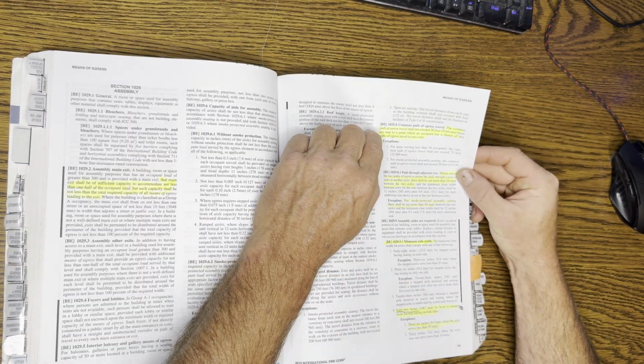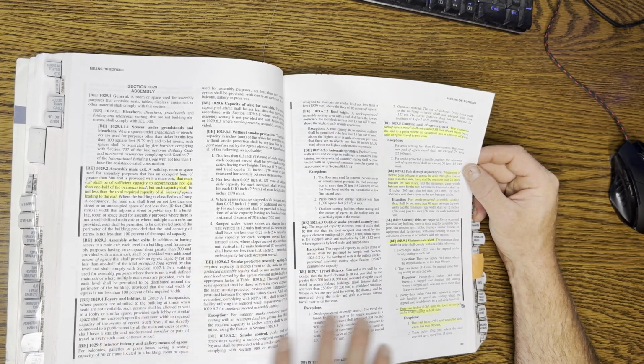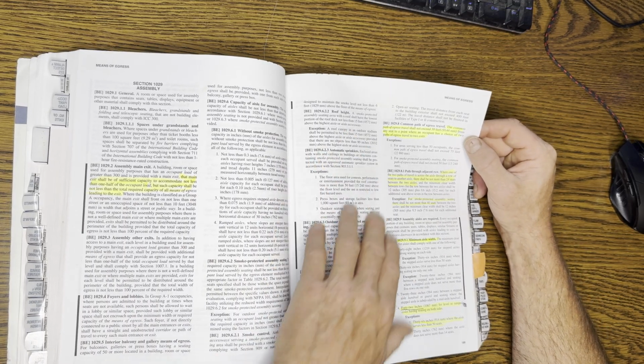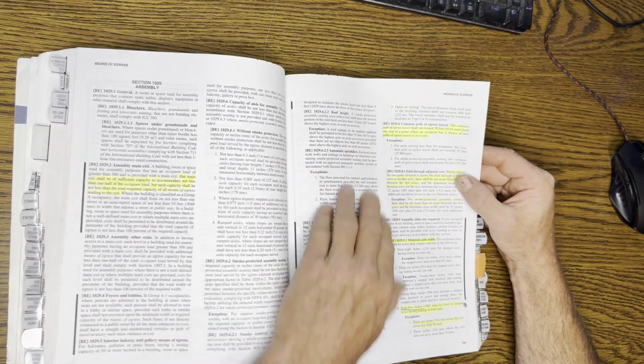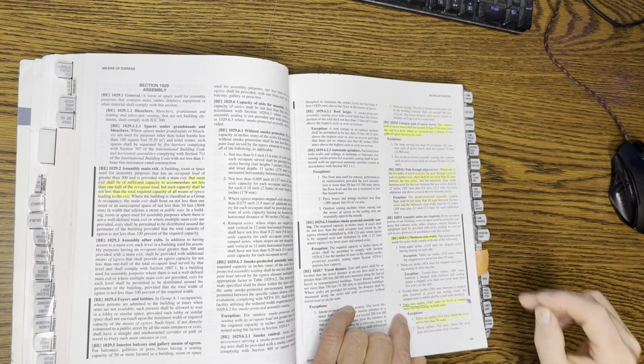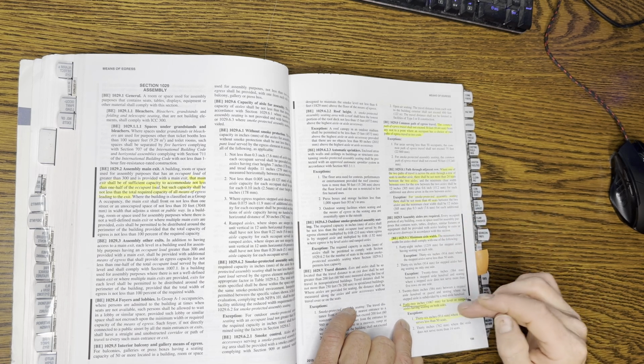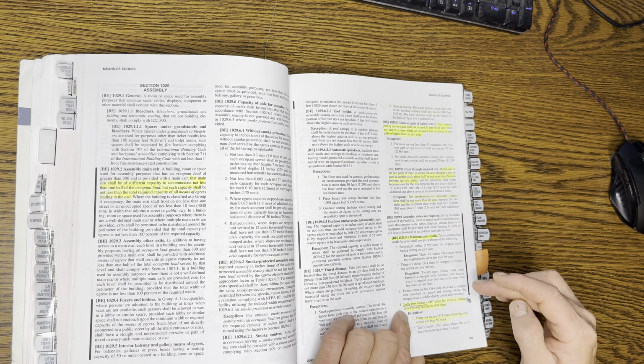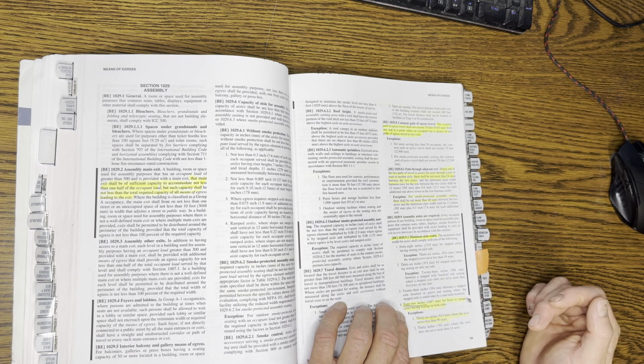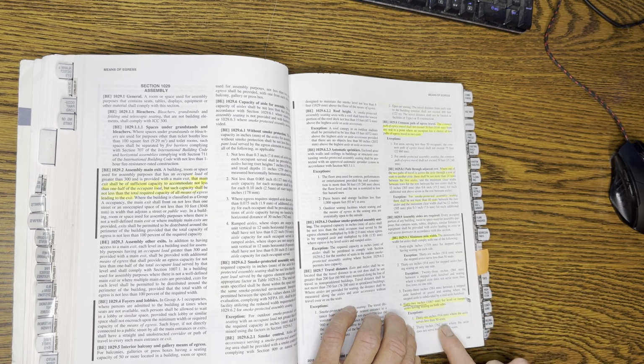Common path of travel shall not exceed 30 feet. Remember, this is assembly occupancy, so it's specific for certain assembly occupancies. There are some allowances here, so read through those. You have aisle seating, and you'll need to calculate aisle seating. So minimum aisle widths: for level or ramped aisles having seating on both sides, you have to have 42 inches for the width of the aisle or the ramp, and 36 inches where the aisle serves less than 50 seats.